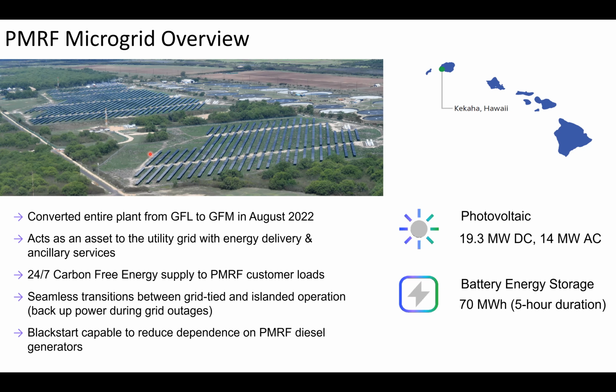Since this power plant is within the Pacific Missile Range facility, which is a naval base out there, it can also provide microgrid services. So if the naval facility needs to run a mission or disconnect from the grid entirely, the PMRF Microgrid helps provide power during an outage or just during their missions while disconnected from the grid. It allows seamless transitions between a grid-tied mode and moving to an islanded mode, and also provides some Blackstart capabilities.